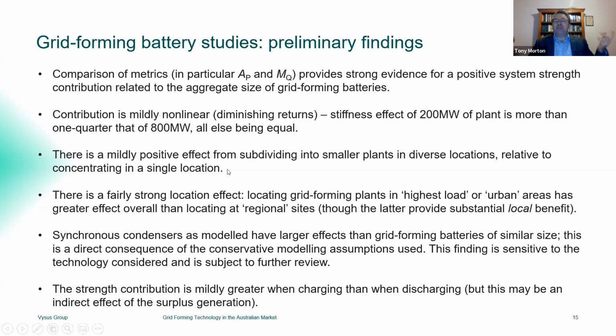And related to that is the third point here, that if we're able to take a given amount of inverter capacity and split that up and spread it around the system at smaller points, again, intuition tells us that we should be able to get a good system-wide contribution from that dispersal of plants. And in fact, we do see that again when we look at the quantitative metrics from our power flow studies. There is a benefit from spreading these out versus concentrating the same overall capacity just at one point in the network.